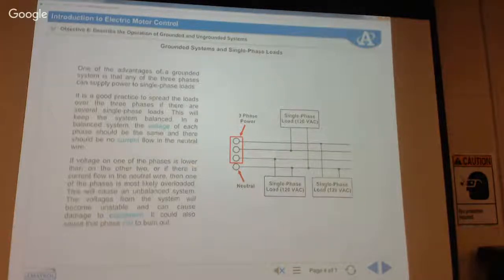When it talks about one of the advantages of a grounded system, any of the three phases can supply single phase power by connecting here and here. They're all going to this neutral wire right here. See that? So we can tap off of here and get 120 volts.